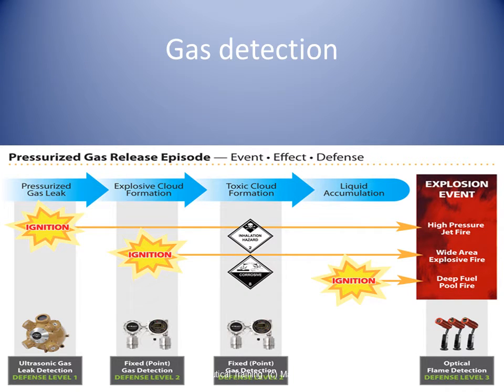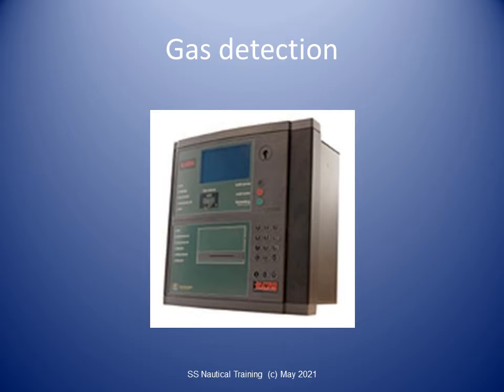The IMO codes call for every gas carrier to have a fixed gas detection system with audible and visual alarms on the navigating bridge, in the cargo control room, and at the gas detector readout location.